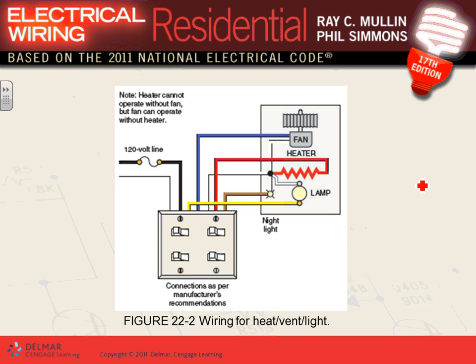Here's that combo that you use wiring for heat, vent. I can't emphasize this enough. The one I want you guys to do in our bathroom is only have a vent and a light, or only vent. I leave it up to you. If you want vent, you just add it to the receptacle, pick it up as one of these receptacle with your receptacle circuit. If it's vent light, you pick it up on one of these lighting circuits that you have, right? One of the lighting circuits.